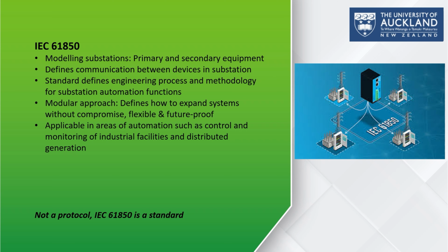One of the core elements of IEC 61850 is that it defines communication between devices in a substation. Instead of relying on traditional hardwiring, the standard uses high-speed Ethernet-based communication protocols. This facilitates faster protection signals, reliable control commands, and real-time monitoring, ultimately improving the performance and safety of the entire substation.